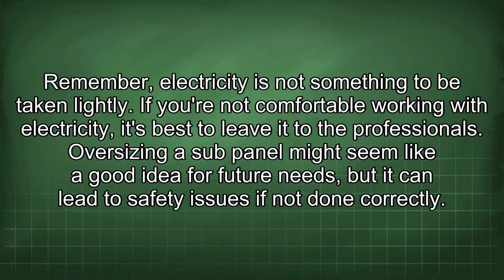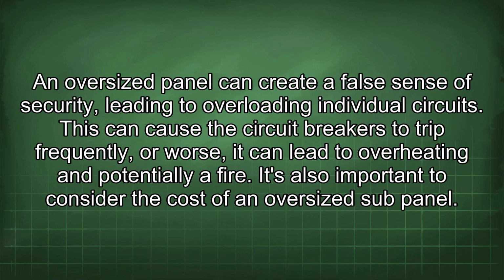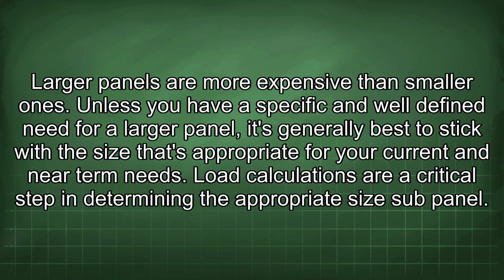Oversizing a sub-panel might seem like a good idea for future needs, but it can lead to safety issues if not done correctly. An oversized panel can create a false sense of security, leading to overloading individual circuits. This can cause the circuit breakers to trip frequently, or worse, it can lead to overheating and potentially a fire. It's also important to consider the cost of an oversized sub-panel. Larger panels are more expensive than smaller ones. Unless you have a specific and well-defined need for a larger panel, it's generally best to stick with the size that's appropriate for your current and near-term needs.